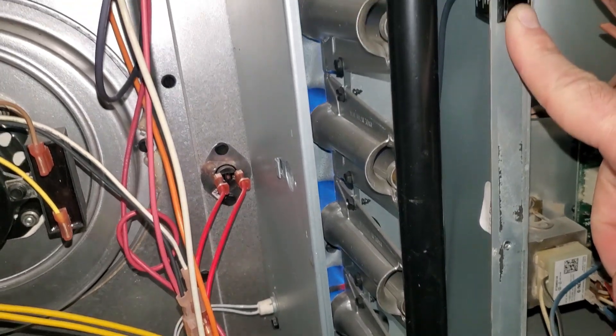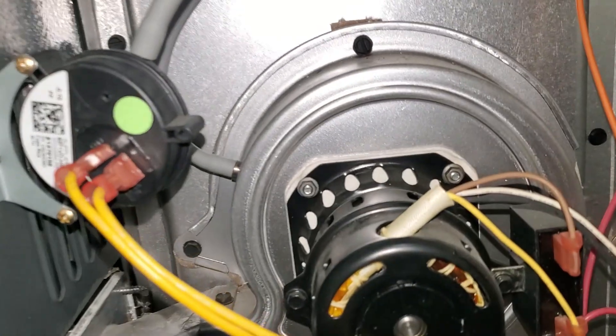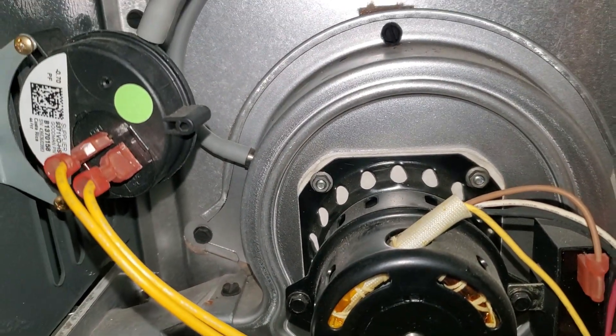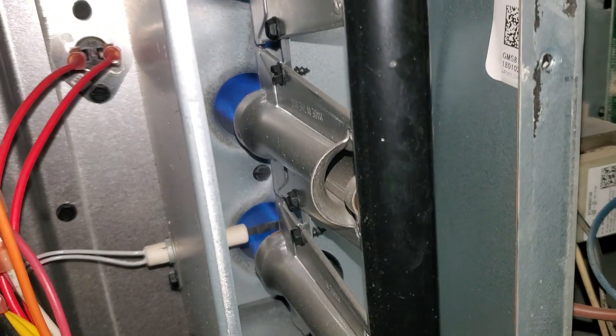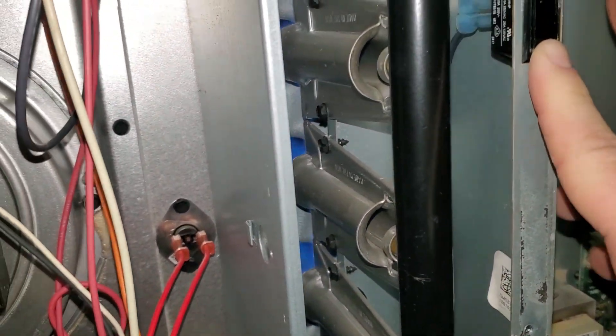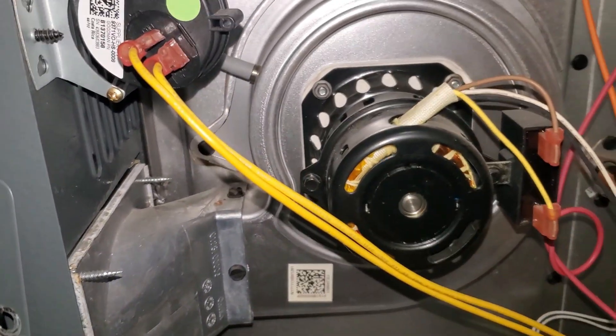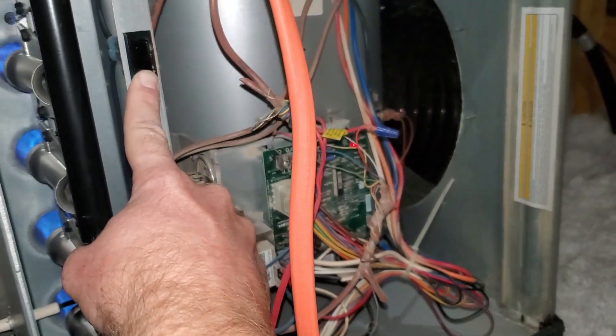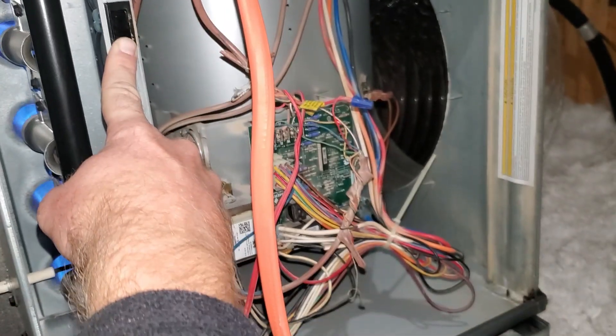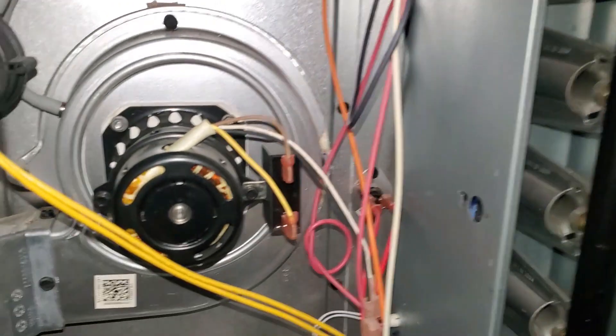There we go — now we have heat! All this was was some blockage down there in that port that needed to be cleared up. Once we did that, we got our furnace back on. Now we've got heat and a warm house. You can also go back and clean that hose or clean that fitting. Our big motor turned on now and it's sucking out the heat and distributing it through the house. This is a fix — I'm glad we got it going. Thanks for watching.